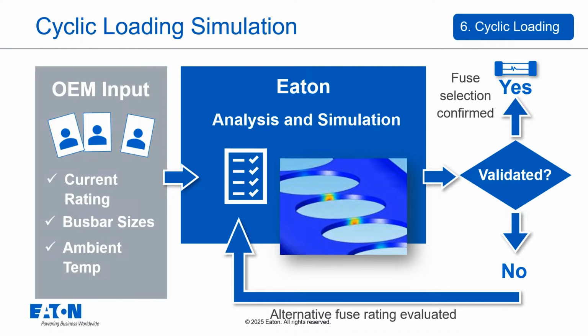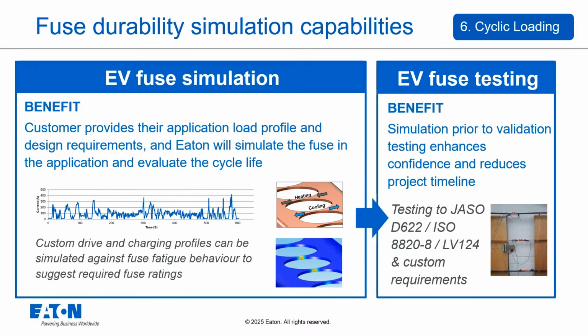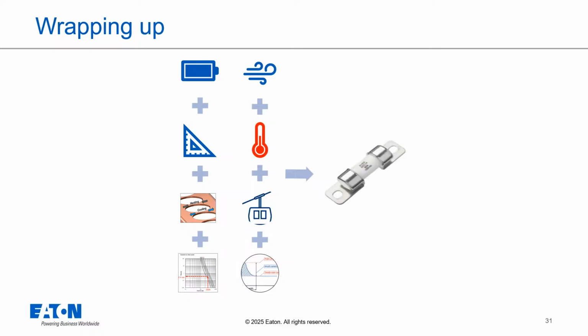Physical testing is still essential, of course, following standards like JASO D622, ISO 8820, or LV 124, along with any custom requirements from the OEM. So, to wrap up based on what we've covered, selecting the right high voltage fuse for an EV is a detailed process that goes way beyond just picking a current rating. It requires careful consideration of voltage, current, fault current, and the challenging operating environment. Derating based on environmental factors is absolutely critical for ensuring reliability and preventing nuisance trips or premature failure. And importantly, accounting for dynamic loads such as overloads and cyclic loading through methods like simulation and testing is essential to ensure the fuse provides the required lifespan in real-world EV applications.